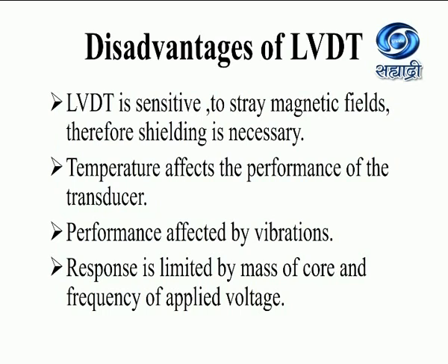LVDT is sensitive to stray magnetic fields, therefore shielding is necessary. It can be affected by magnetic fields. Temperature affects the performance of the transducer. Performance is also affected by vibrations. And the response is limited by the mass of the core and the frequency of the applied voltage. So these are some disadvantages of LVDT.